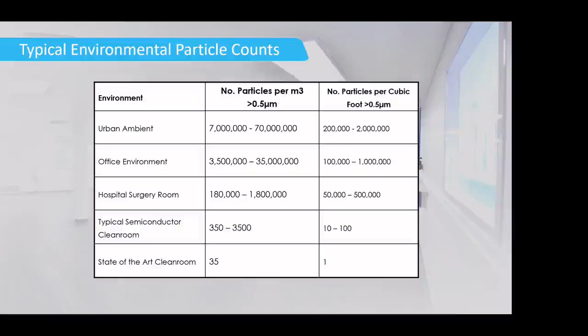And to put it into another perspective, in a typical urban environment you're looking at up to 70 million particles per cubic metre of air. An office environment, up to 35 million. Surgery takes place in an environment with up to 1.8 million particles per cubic metre, which sounds a lot, but that's a validated and proven strategy that that level is clean enough that human beings can fight off any remaining potential pathogens. But for semiconductors and absolute top state-of-the-art clean rooms, we're talking tens or hundreds of particles per cubic metre.